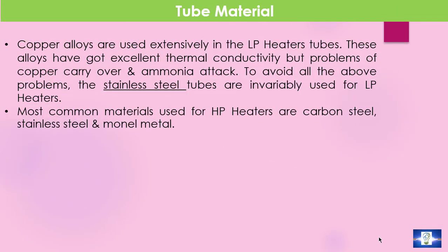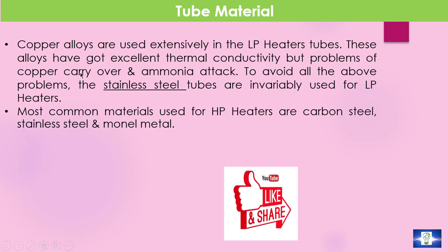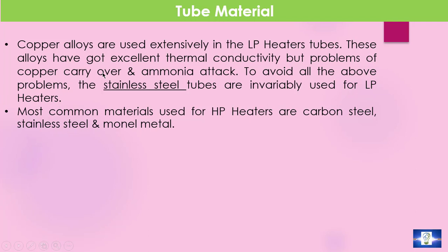Tube material. Both copper alloys and non-ferrous alloys are used for LP heaters and HP heaters. Copper alloys are used extensively in the LP heater tubes. These alloys have excellent thermal conductivity, but on the other hand, they have problems of copper carryover and ammonia attack, which may require a complex boiler cleaning after short intervals. To avoid all these problems, stainless steel is inevitably used for LP heaters.